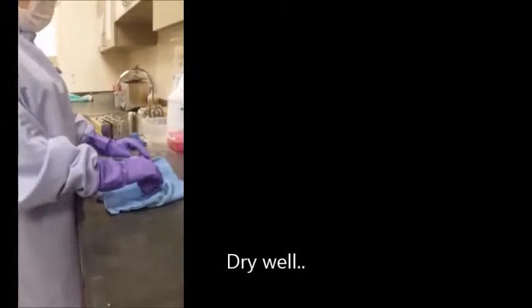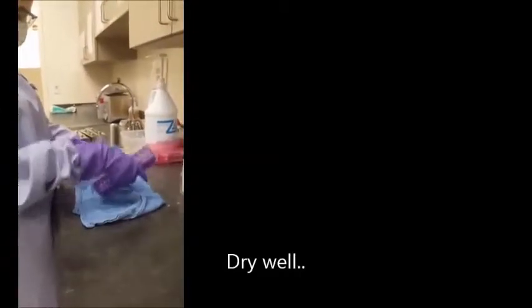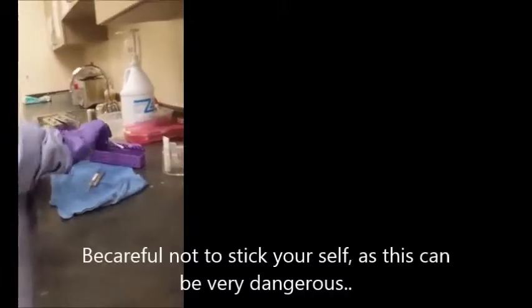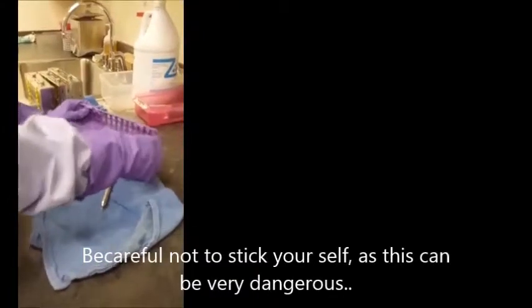Dry the cassette and instruments with a blue towel. At this time, examine your instruments for any missing or damaged pieces and replace as needed. This will also be the time to lubricate any instruments to prevent rusting. Place a sterilization strip in the cassette and close the cassette. Wrap the cassette with the sterilization paper to prepare it to be autoclaved.